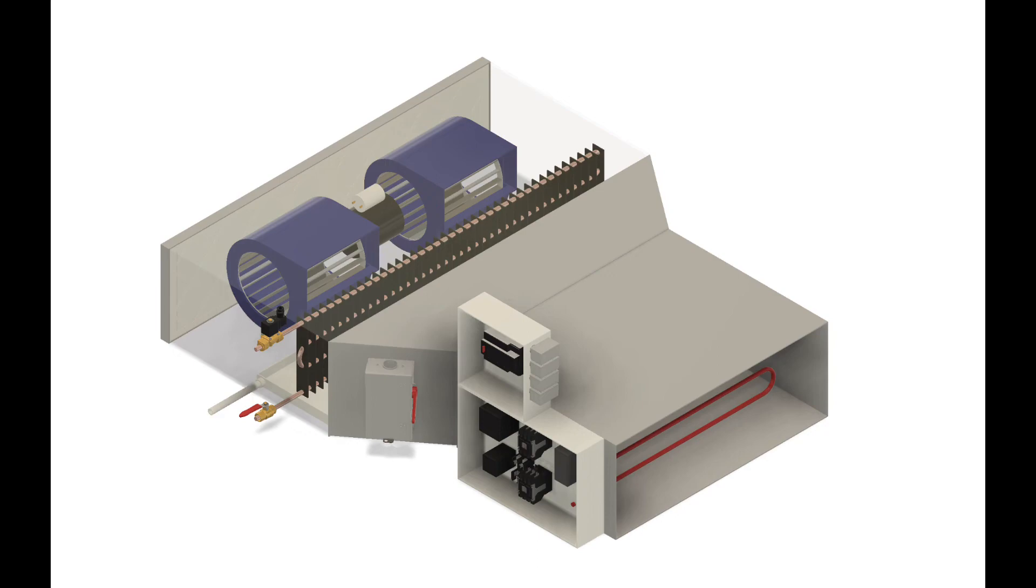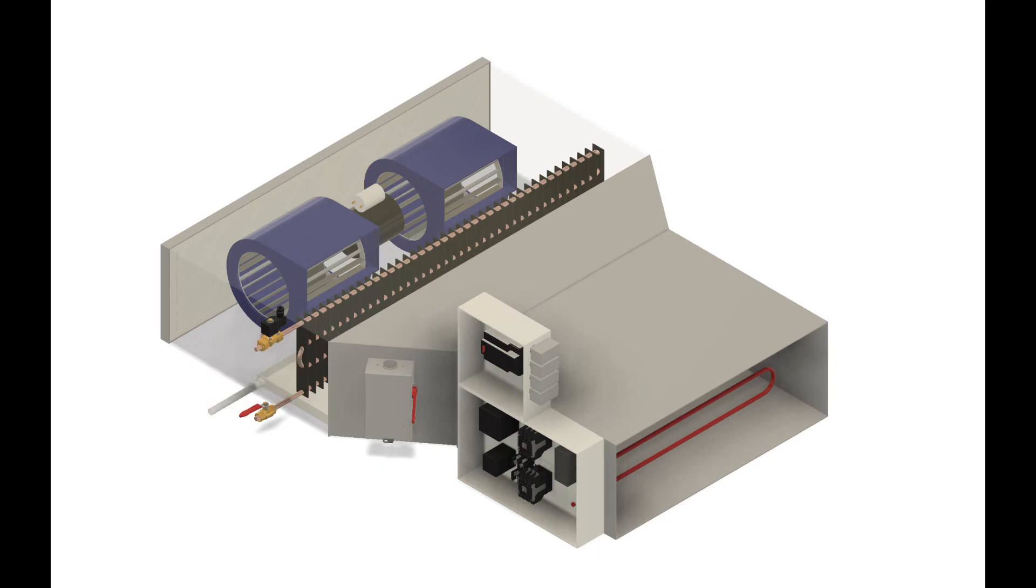Now moving on to a no cooling condition. Again, you can see the cooling coil here. Some of the same things to look for are the filters plugged and dirty. Is the blower motor running? Is the coil itself plugged with dirt and dust and need to be cleaned off?